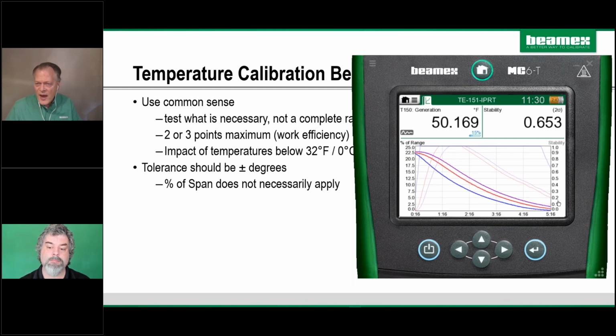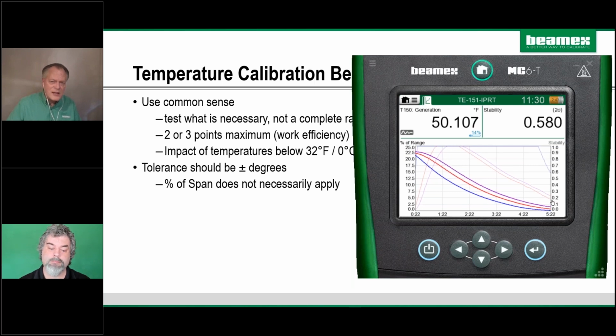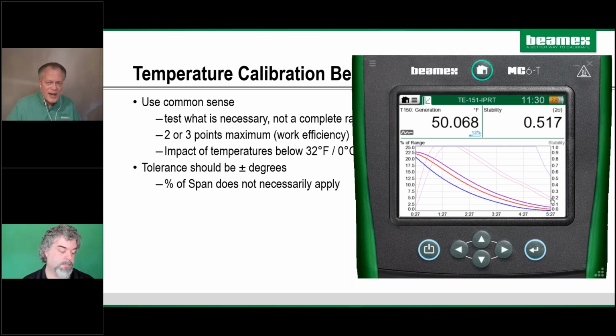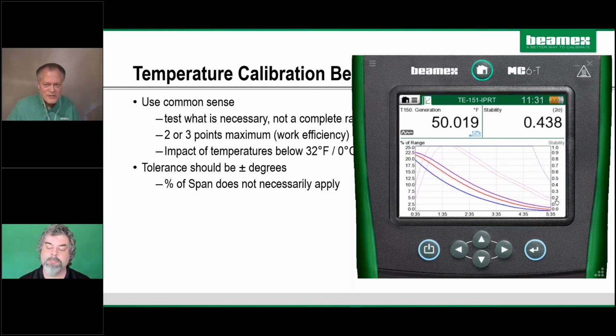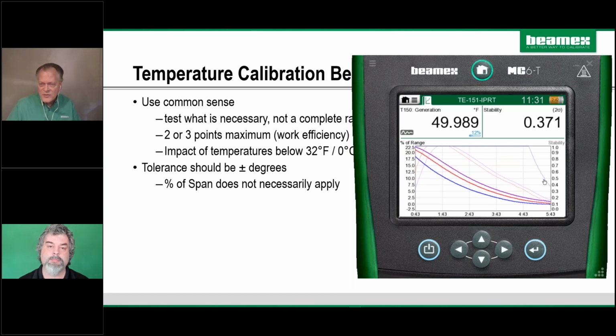But the stability factor, you see it says 2 sigma. So we're calculating the standard deviation over the last minute, and then we double that calculation to give you a stability factor. So this is essentially degrees F. We're saying that our stability is better than 0.2 degrees F with the field probes, but our internal reference is not very stable at this point. But we don't really care, since we have the red reference probe. That's what we're going to be logging as our traceable temperature.